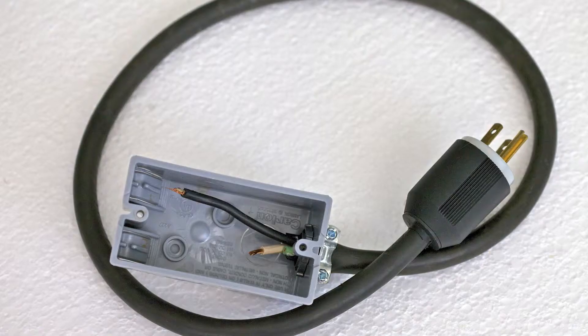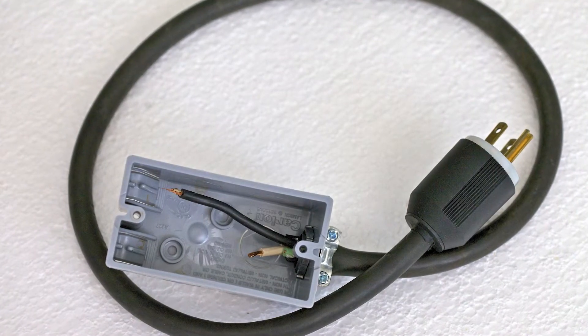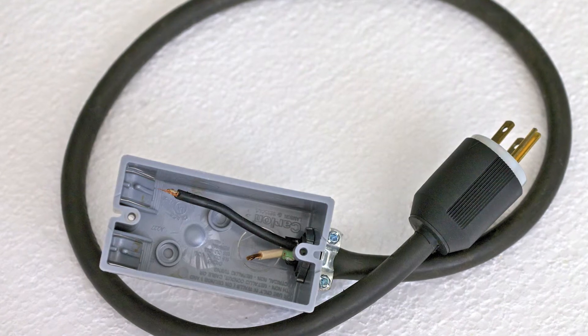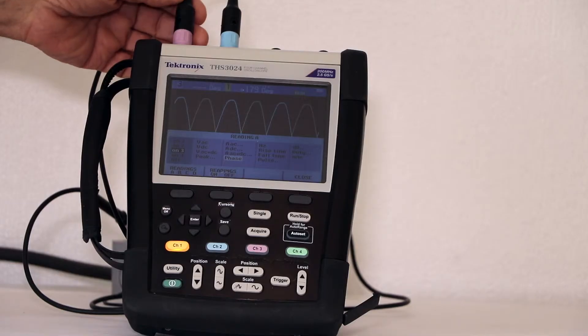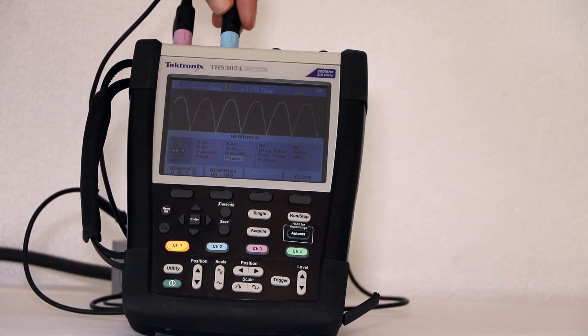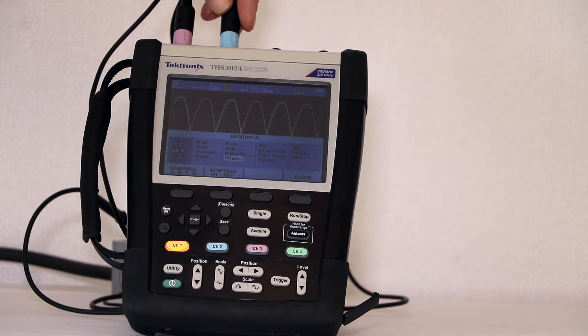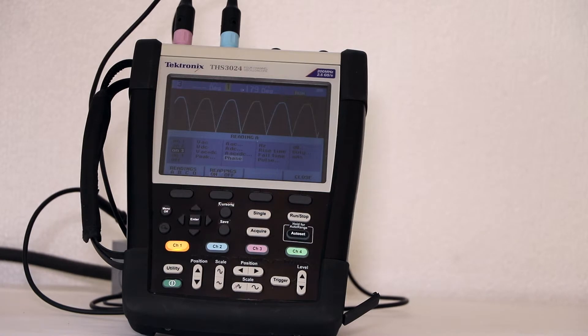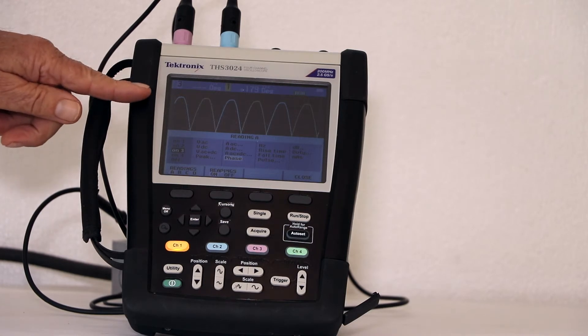For this demonstration, we have connected the channel 1 probe to utility power as accessed via a branch circuit. The probe tip is connected to the black wire, and the return lead is connected to the white wire. The channel 2 probe is connected to the same utility power source, but the probe tip and ground return lead connections are reversed with respect to the branch circuit black and white wires. Consequently, the two waveforms, as displayed, are shifted one half cycle.